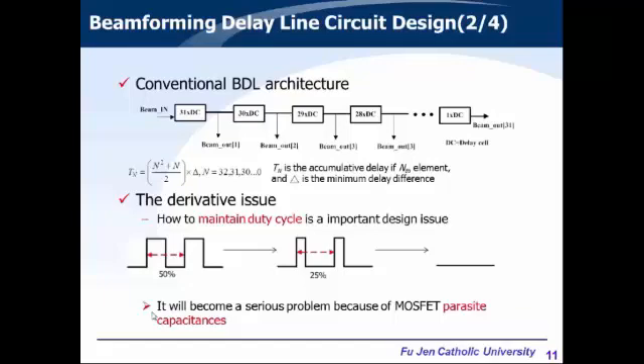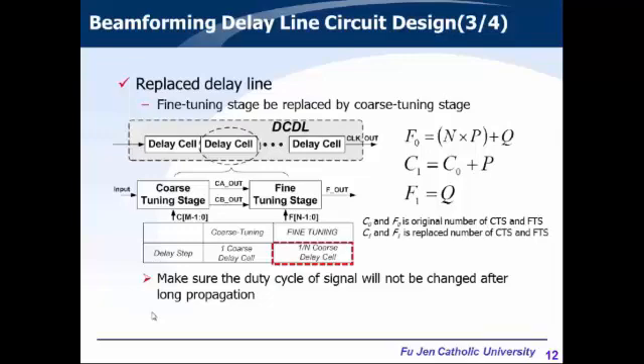The number of delay cells for each channel forms an arithmetic sequence. However, this beamforming uses too many delay cells, which brings derivative problems. The duty cycle cannot be maintained after long propagation and will degrade, and this problem becomes more serious when considering parasitic capacitances. To address this, we replace the fine-tune stage with the coarse-tune stage, because the coarse-tune stage is more stable. According to the delay table, the delay of the fine-tune stage is one order of the coarse-tune stage, so we can replace fine-tune stages with coarse-tune stages.